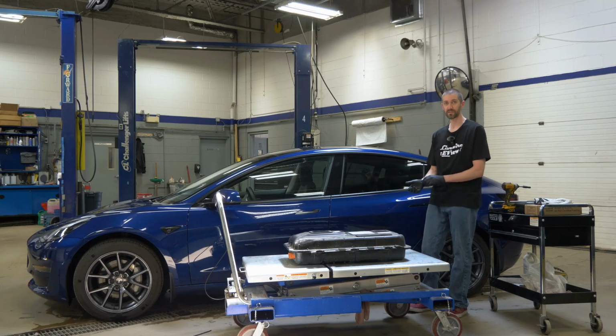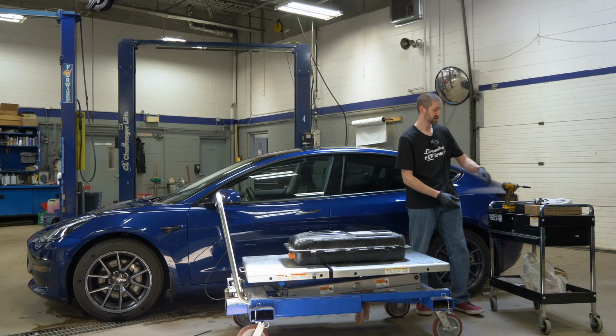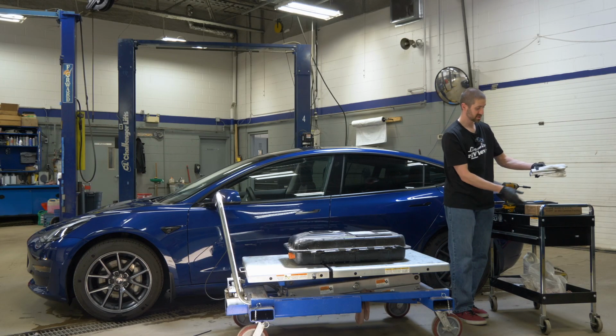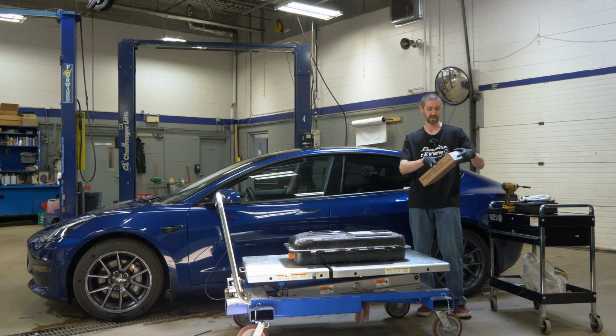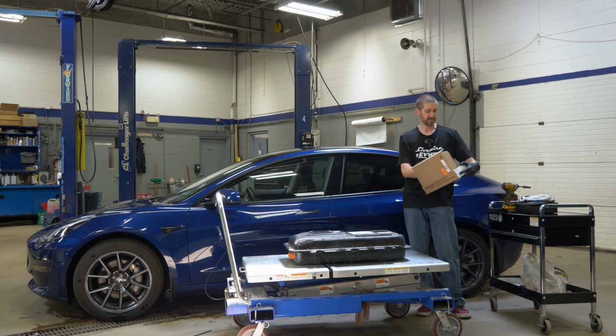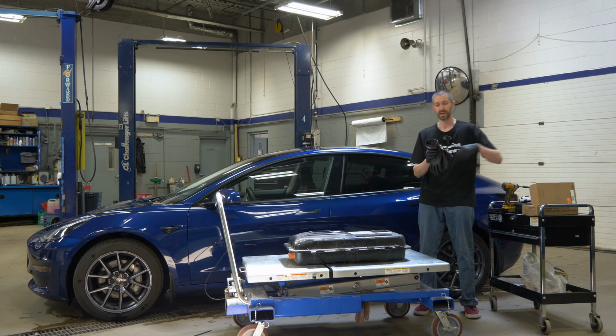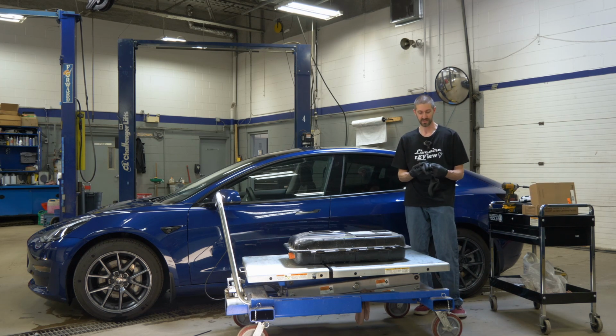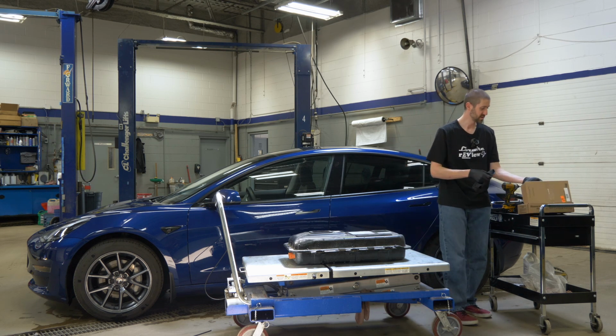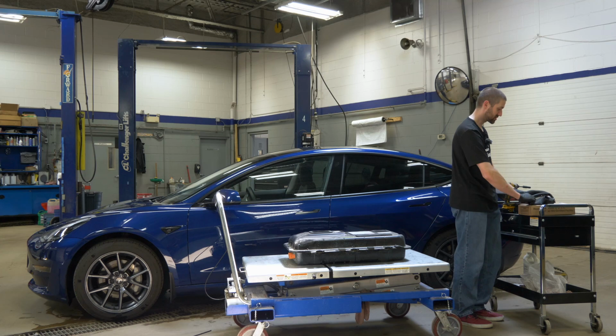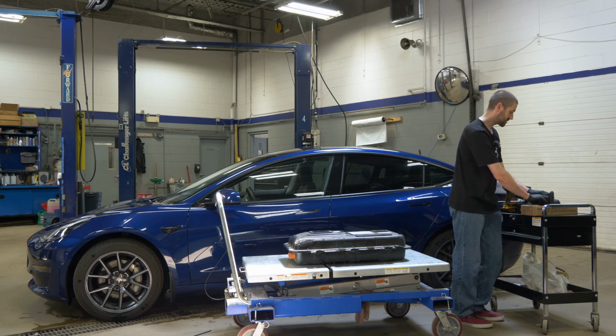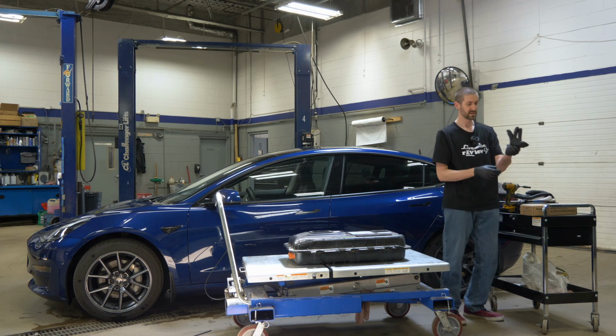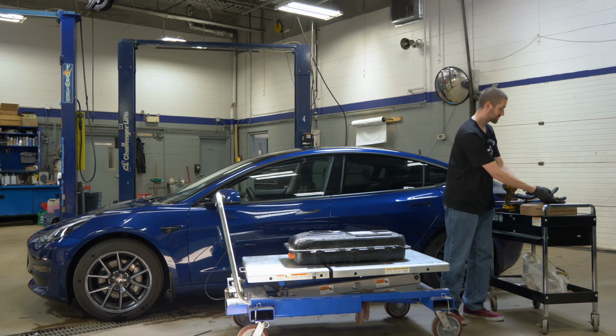So this is a live battery, so first thing we're going to do is get our high voltage gloves on, and we're going to check and see what kind of voltage we have to work with. Now, high voltage gloves have to be recertified every 6 months. And before you use these gloves, you actually have to check for leaks. So what we do is we put them inside out and roll them up in order to create an air bubble so that we can see if there are any leaks. You just roll it up until all the fingers come out, and that proves that there are no leaks in here.